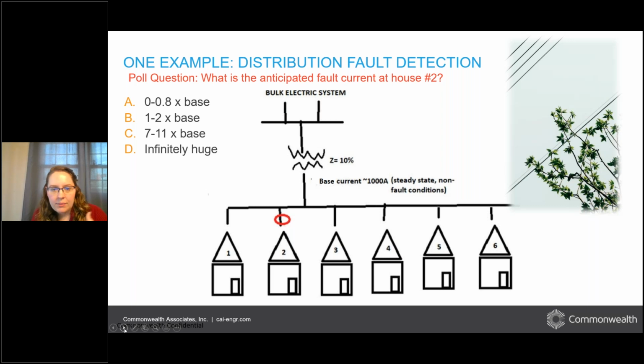And it's also very common to protect us from that kind of situation by using a fuse. So on that little branch where the red circle is, in a typical distribution system, we might see a fuse that's supposed to melt when the amperage is above 1,000 amps, and hopefully before we reach 10,000. The fuse would melt, it would drop house number 2 off of our grid, off of our circuit, and then power would continue to flow to the other houses coming from that bulk electric system. This is what many of us in the power industry have come to know.